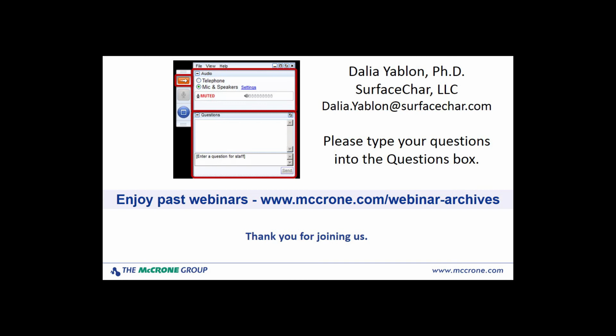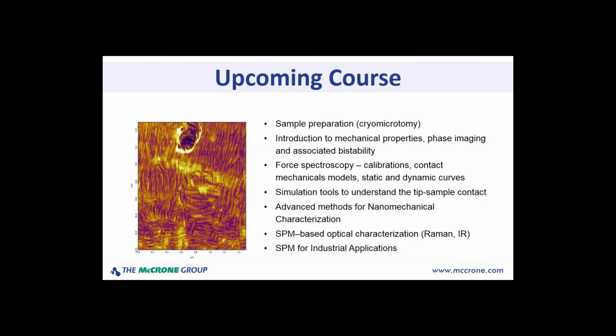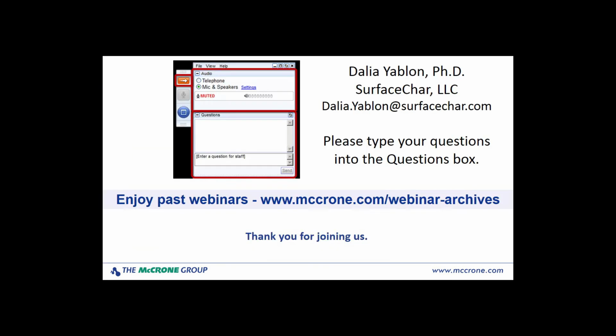Another question: if the minimum resolution is 5 nanometers, can you still get topography at the lower resolution limit? Resolution is always kind of a tricky subject for most microscopists. The reason I say 5 nanometers is that is really for commercial instruments with commercial levers not operating in some super fancy modes. If you want to operate in a more sophisticated mode and you have a real first class research instrument, you can certainly get topography below that. In air, AFM research level instruments under certain conditions and with more sophisticated modes can get atomic scale resolution. That's really been around probably the past 5 to 8 years. It will be sample dependent.